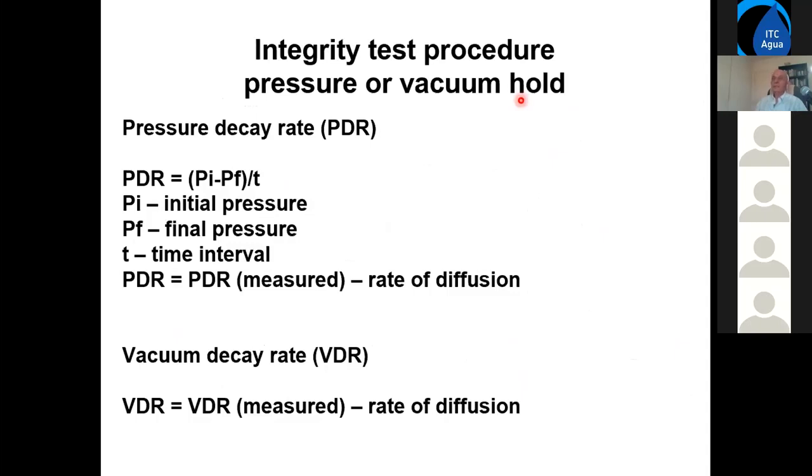Now the membrane filtration, as I said, produces water without colloidal matter, but only under the condition that the membrane has good integrity. For potable application, the system operator is obligated by regulation to test integrity of the system daily. There could be different methods of testing integrity. The most common is pressure decay. So the system is drained of the water by applying clean air pressure. Then all the valves are closed, the system is pressurized for 5 minutes, and the rate of the pressure drop indicates the integrity. The integrity is calculated by the PLC. So software calculates integrity.